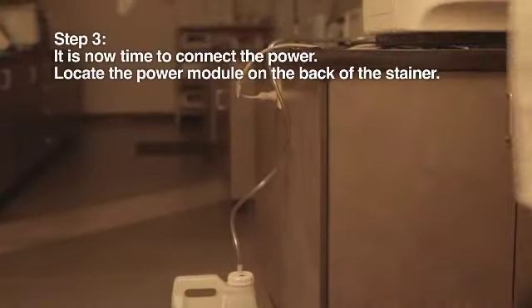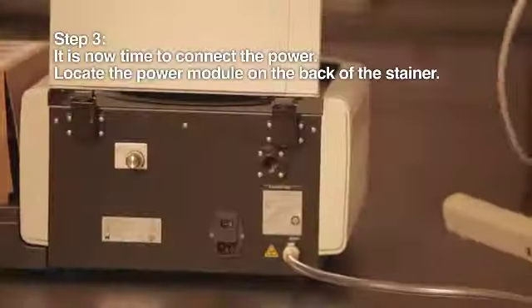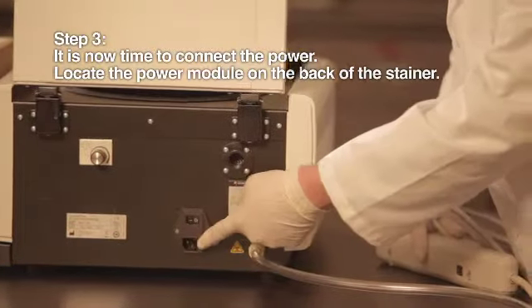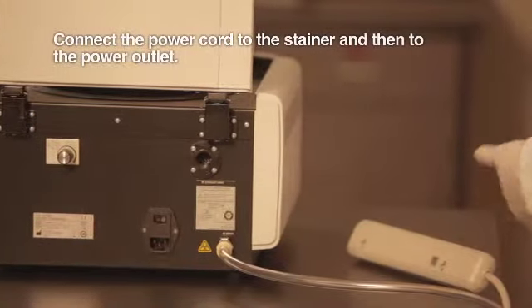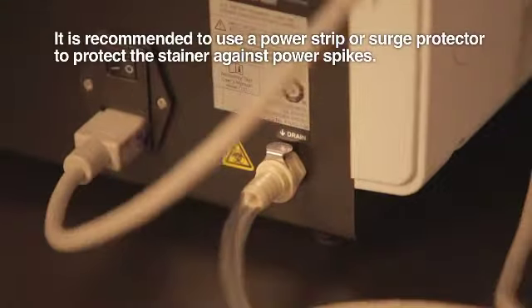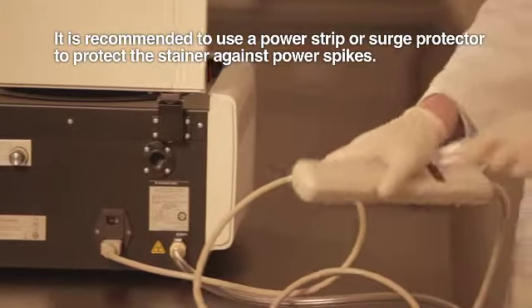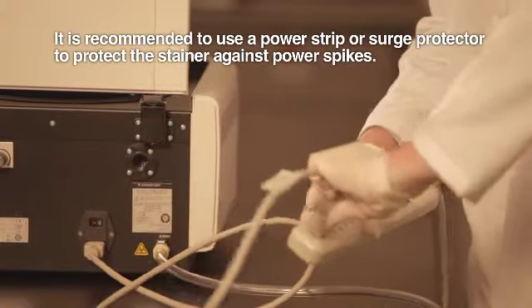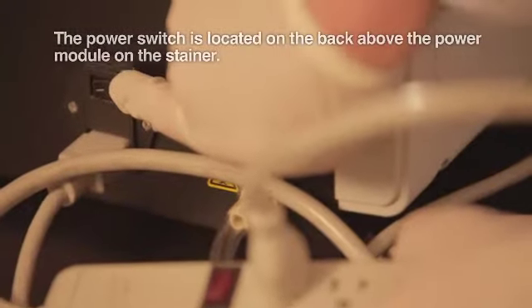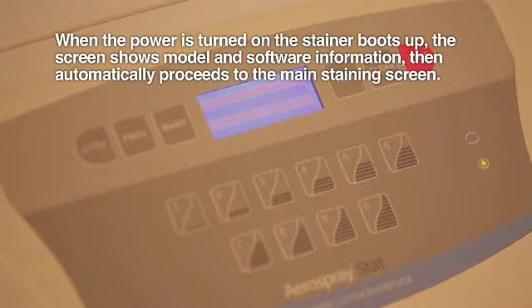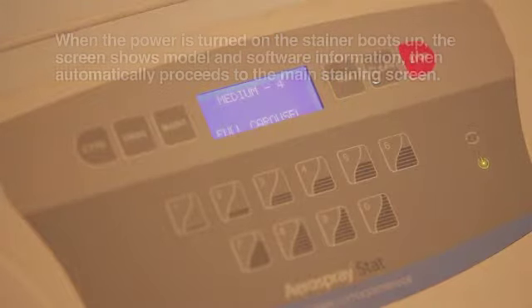Step 3. It is now time to connect the power. Locate the power module on the back of the stainer. Connect the power cord to the stainer and then to the power outlet. It is recommended to use a power strip or surge protector to protect the stainer against power spikes. The power switch is located on the back above the power module on the stainer. When the power is turned on, the stainer boots up, the screen shows model and software information, then automatically proceeds to the main staining screen.